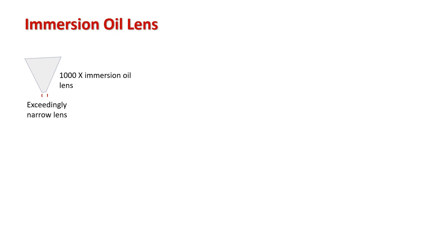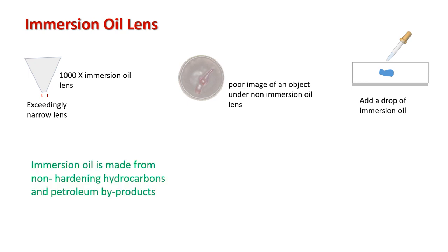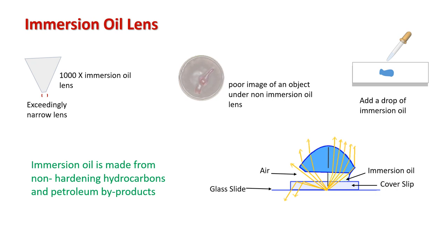However, the oil immersion lens is exceedingly narrow and most light misses it, so the object is seen poorly and without resolution. To overcome this issue, the lens is used with a drop of immersion oil. Immersion oil is made from non-hardening hydrocarbons and petroleum byproducts, and it is placed between the lens and the glass slide. Immersion oil has the same light-bending ability as the glass slide, so when light passes through it, it keeps the light in a straight line that falls on the lens, and resolution becomes clear.